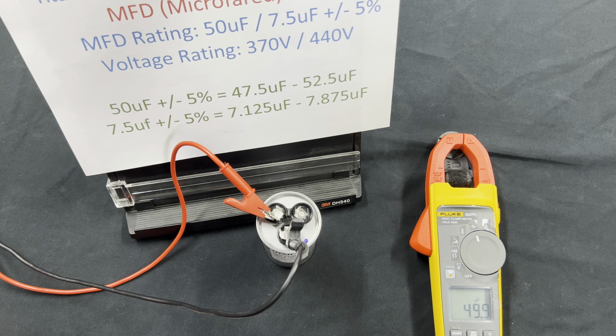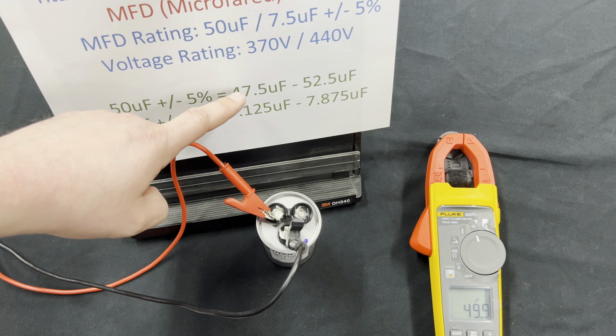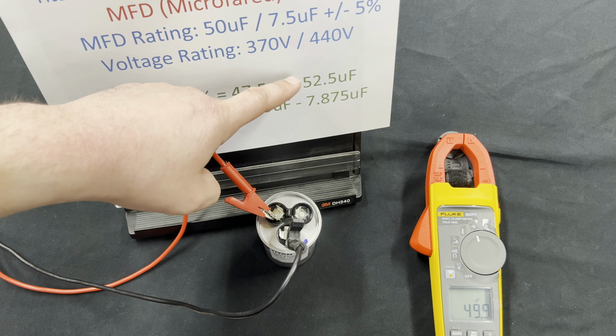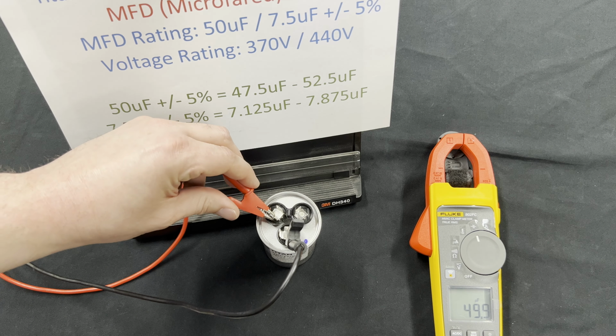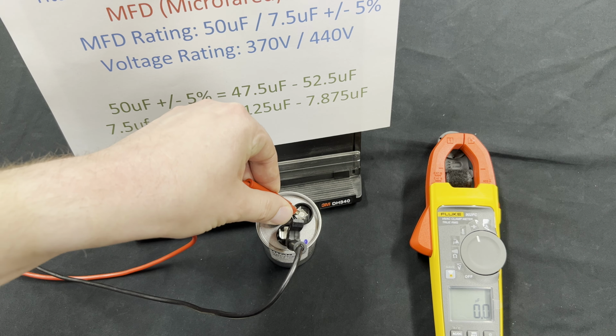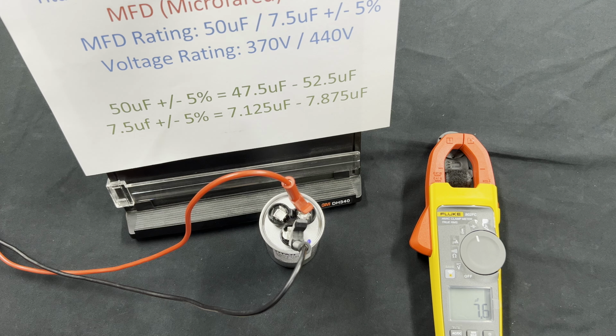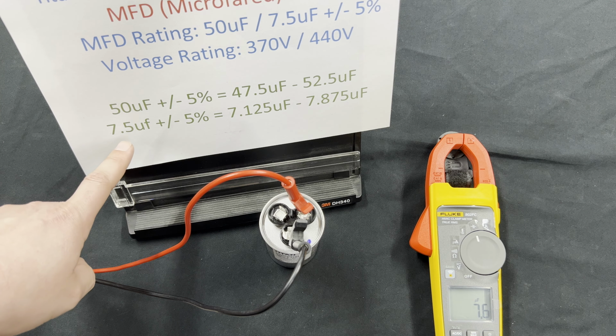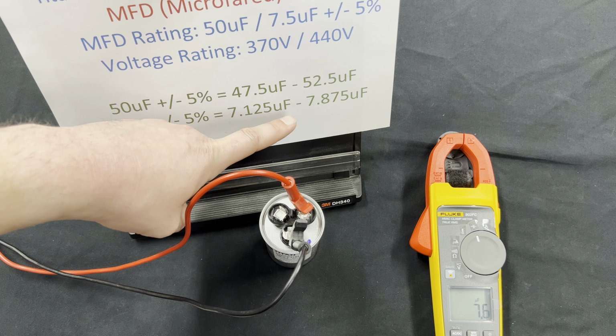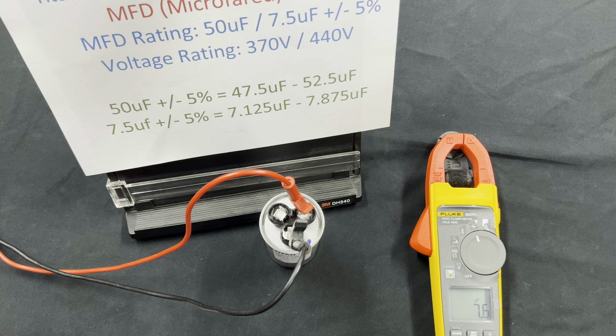We get 49.9, slightly less than the rating, but well within the 5% range. Next, we'll take the probe and shift it over to the condenser fan motor terminal, and we get 7.6, slightly more than the rating, but again, well within the 5%. That's all there is to it when it comes to testing a run capacitor. Hopefully this video was helpful.